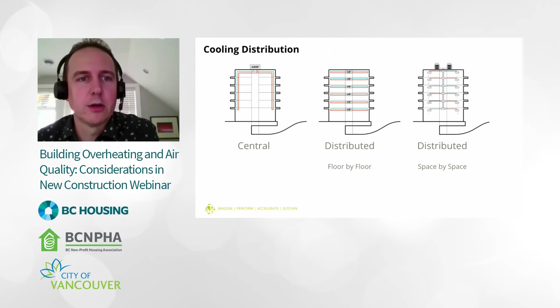The middle image here is the floor-by-floor, where you have a very simple heat pump, and that's providing cooling on a per floor basis. It can be very cost effective, but does take up space on the floor plate potentially. Something to be considered. How do you maintain the equipment if it's all distributed through the building? These things need to be factored in. And then you've got the specific space by space, where each individual user or occupant would have the ability to control and change their space accordingly. Typically, the more control and flexibility you provide, the more the capital cost and the complexity increase. But again, it's understanding what the risk of overheating is, and what is the most appropriate way to mitigate it will be dependent on the project context.